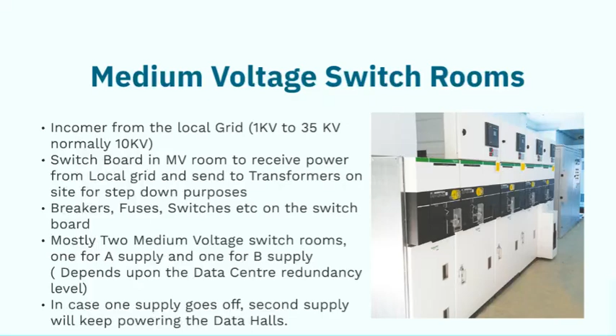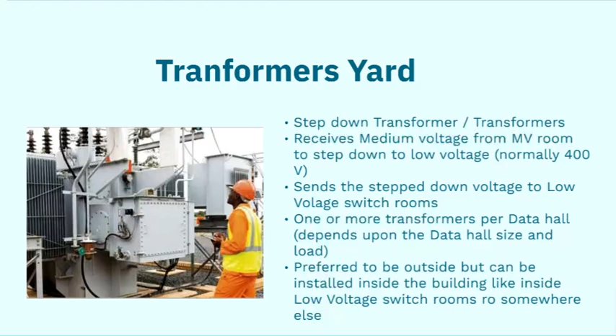So in a transformer yard, there can be many transformers. It all depends upon the data center demand, upon the data center IT load. In a transformer yard, voltage received from the national grid, which is medium voltage, is converted into low voltage. So the first thing is the medium voltage switch room, second thing is the transformer yard.